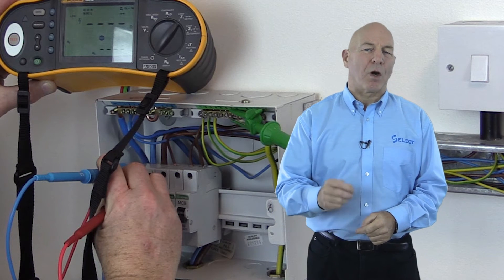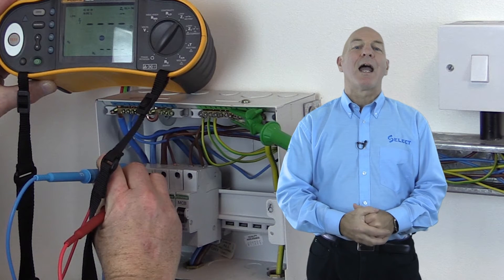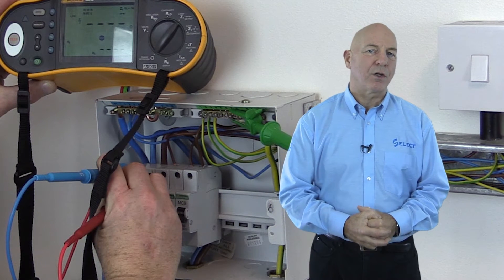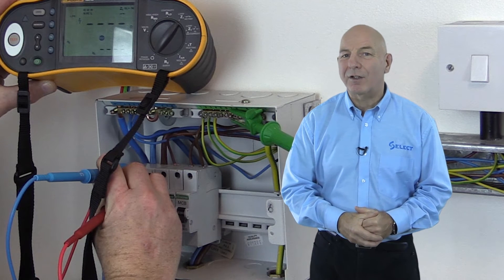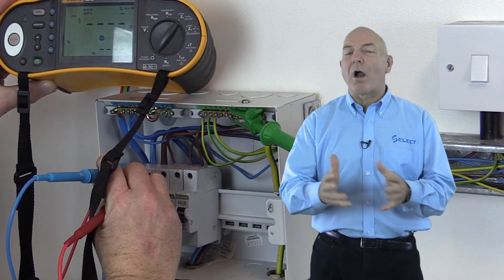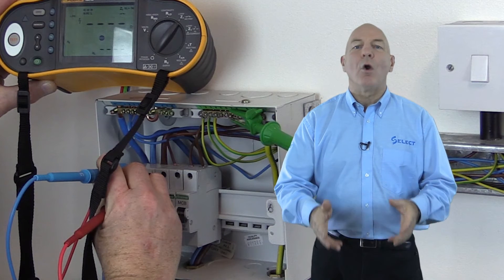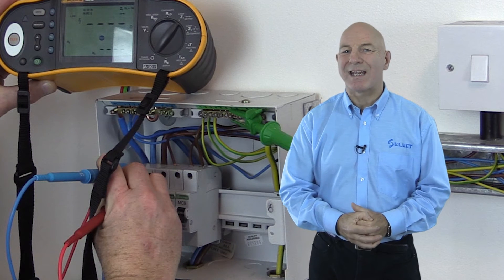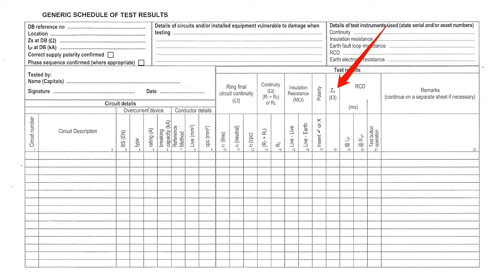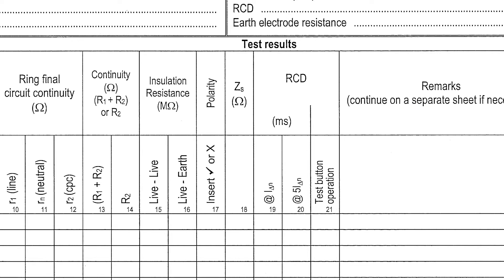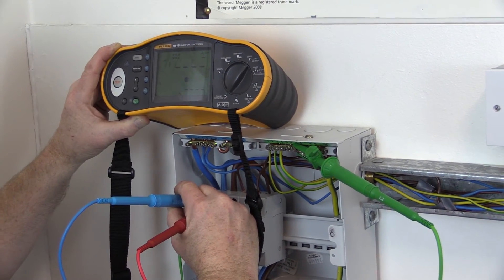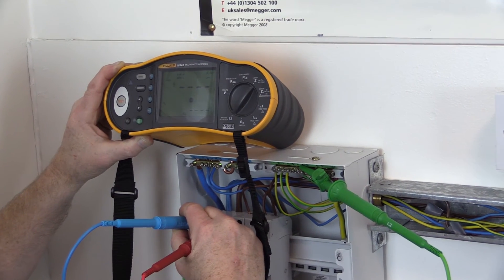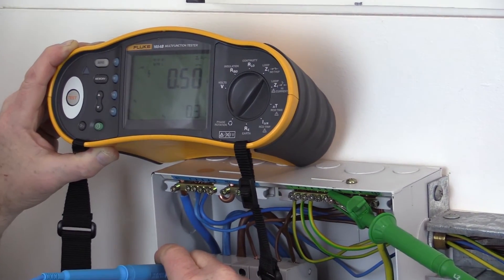The second part of the earth fault loop impedance test is to determine the earth fault loop impedance at the furthest part of each circuit. As noted during the demonstration of testing the continuity of protective conductors test method one, which measures R1 plus R2 of the final circuit, we can simply add this value to the measured ZE value and record it as the earth fault loop impedance ZS of the circuit in the appropriate column of the schedule of test results. Alternatively, we can measure this using the earth fault loop impedance tester at the furthest part of the circuit, and we'll demonstrate this difference on the distribution circuit supplying the single-phase distribution board.